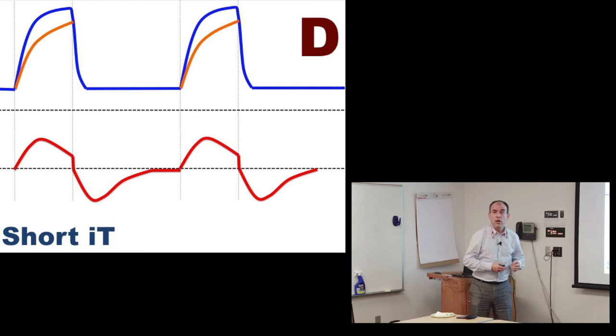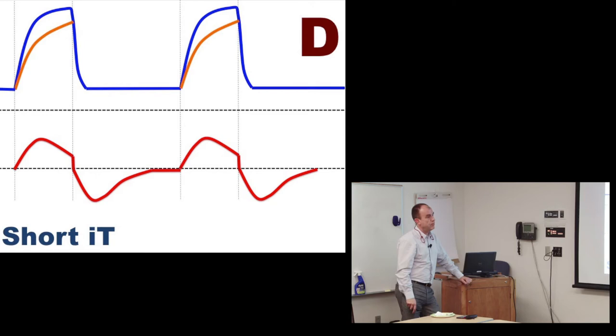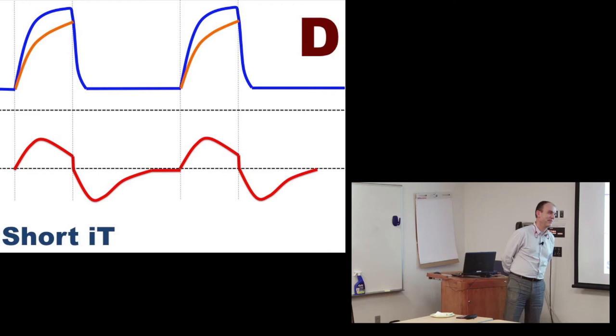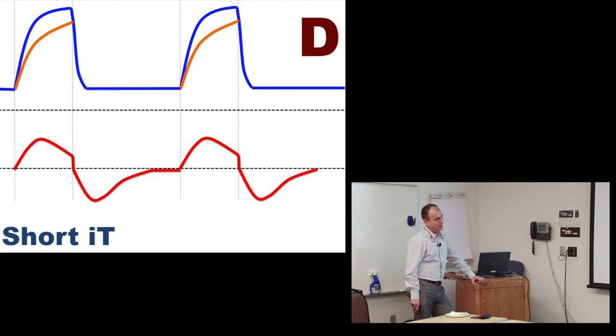I generally set the termination at 10-15% — I don't see any benefit of increasing above that. Regarding pressure support with large ET tube leaks: I had a neonatologist asking why mean airway pressure was higher in pressure support than in conventional ventilation. Looking at the flow tracing, it was clear — because of the leak around the ET tube, the ventilator kept blowing air until the next breath started. Flow came down about halfway and then continued because it could never get to the 15% of peak flow threshold.